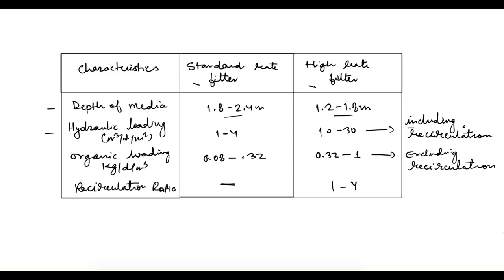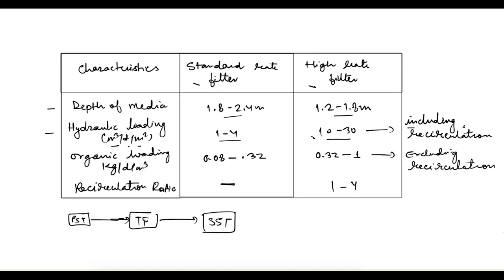Next is hydraulic loading, given in cubic meters per day per square meter. It is between 1 to 4 for standard rate filters and 10 to 30 for high rate filters. This hydraulic loading includes sewage flow through recirculation — that is, if this is your trickling filter with a secondary sedimentation tank after it and primary sedimentation tank before it, some flow comes back. The hydraulic loading includes both QS (raw sewage flow) as well as QR (recirculated flow).